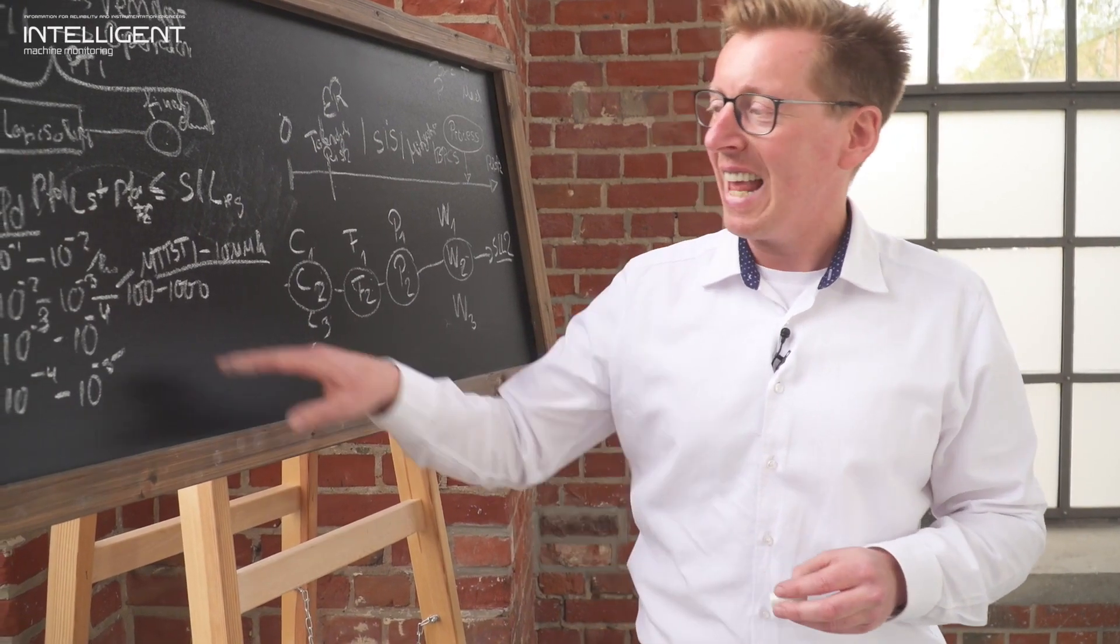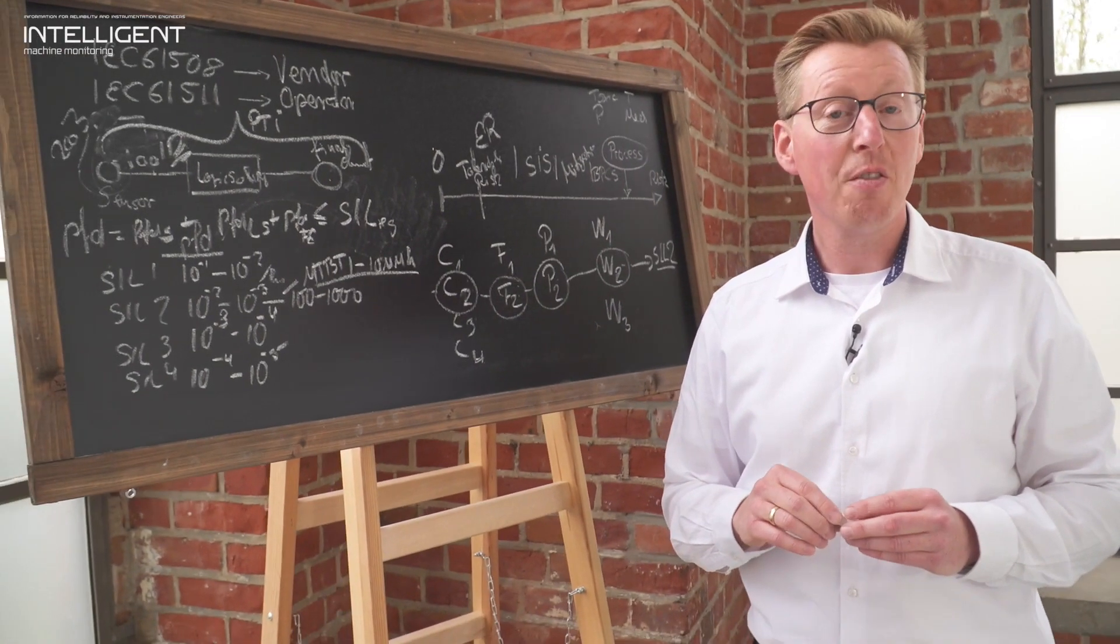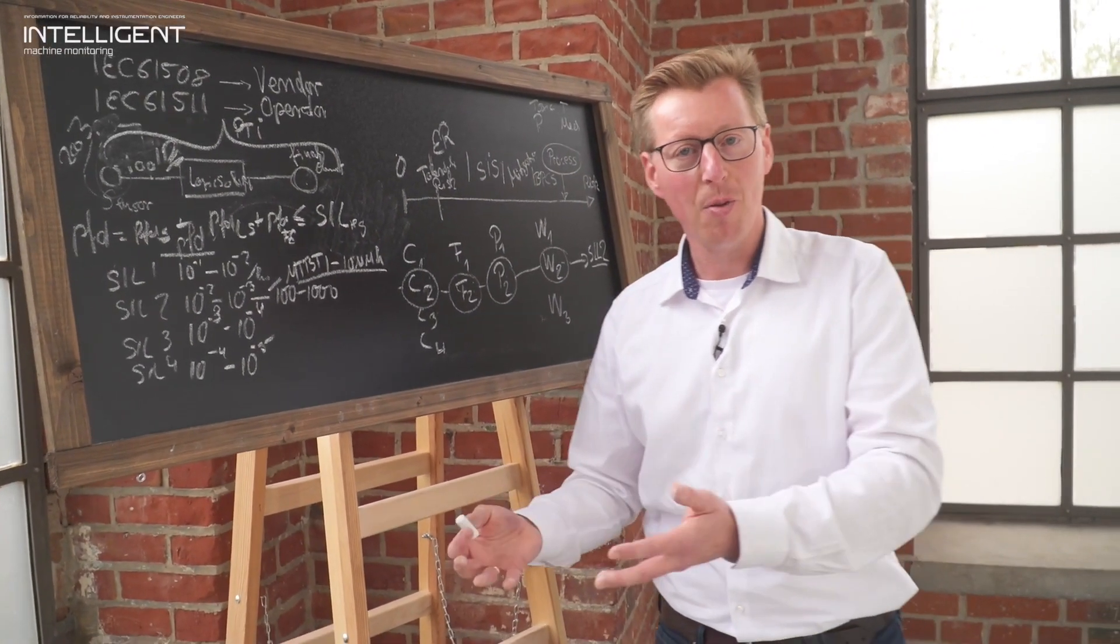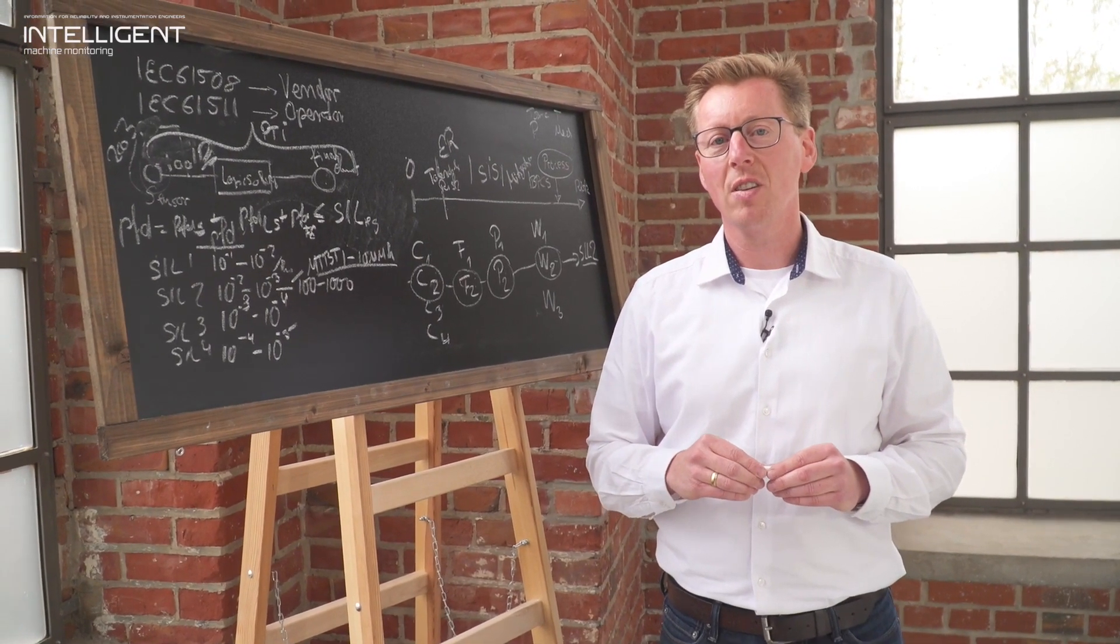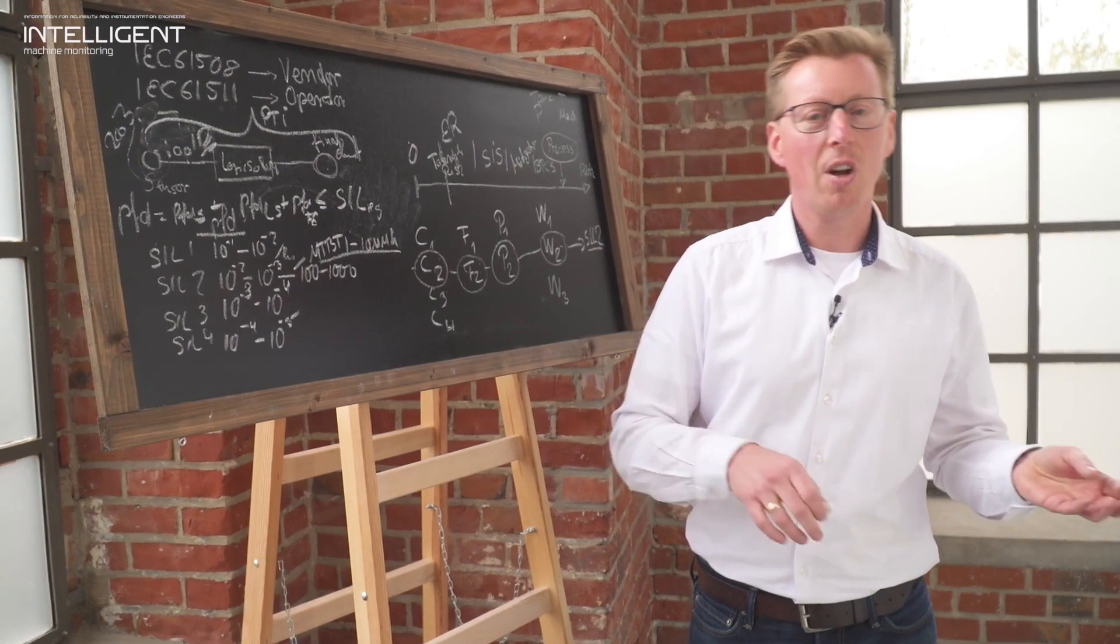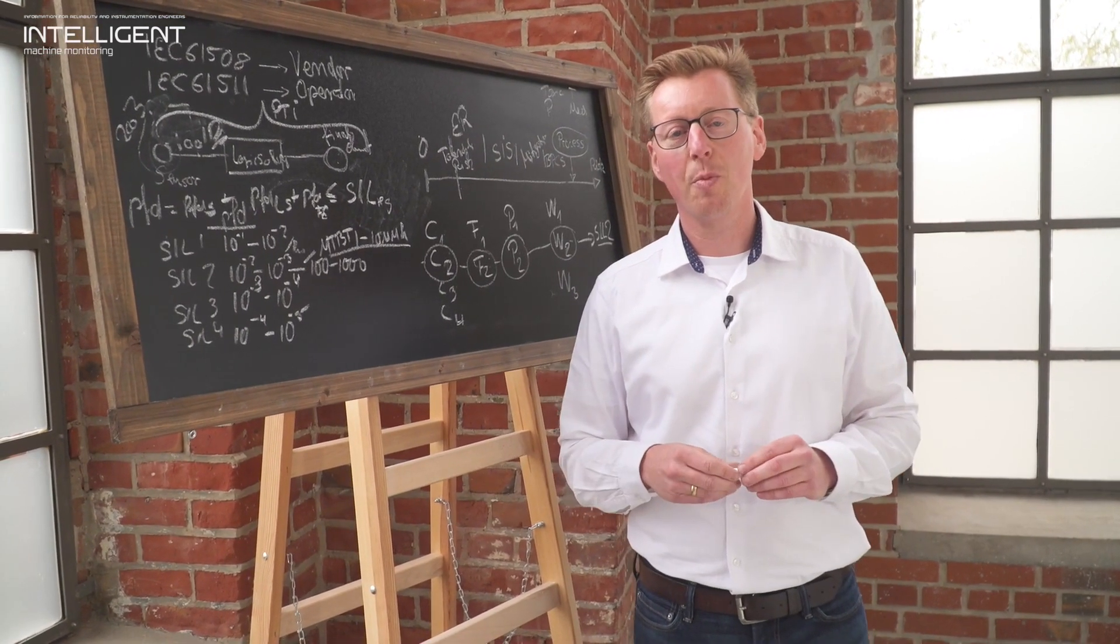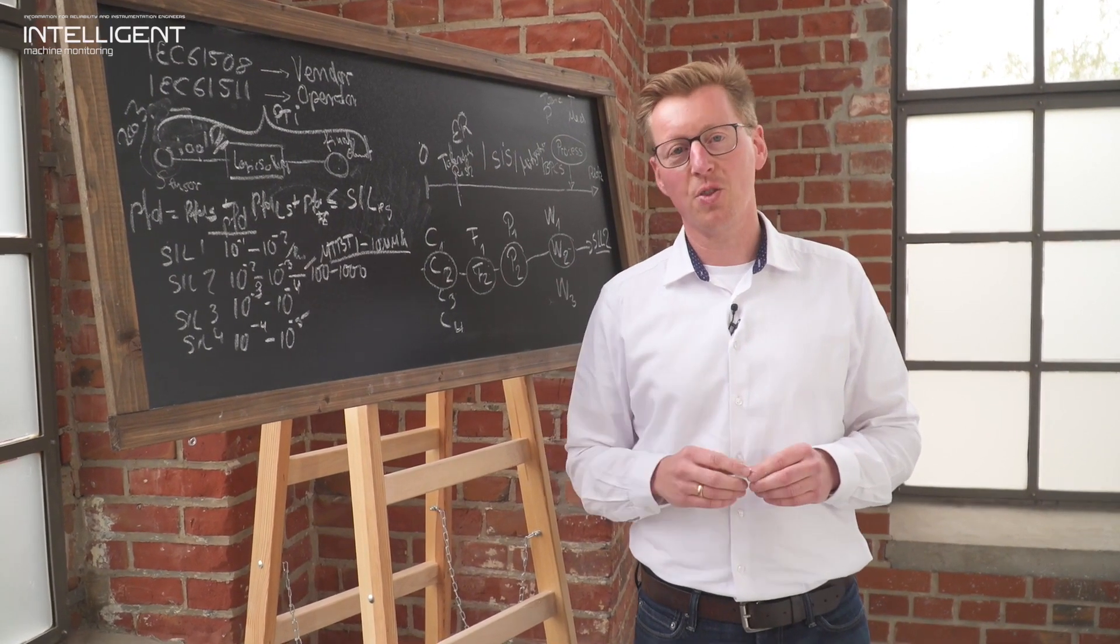Another comment, a highly SIL rated system does not mean that the system effectively captures the problem. It only means that it is likely or very highly available when it needs to be. But as I mentioned in the previous example, a simple temperature sensor, a frame velocity sensor on a machine will not catch problems early enough to prevent the catastrophic event.